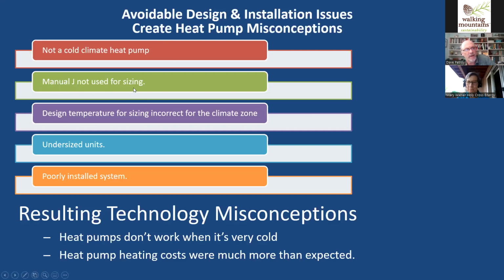Another issue is not sizing it right. There's something called Manual J, which is used for all heating and cooling sizing—not just heat pumps, but furnaces and air conditioners too. That's the tool used by the industry. You've got to make sure the design temperatures are right for your climate zone, 6 and 7. If this isn't done right, the result is undersized units.